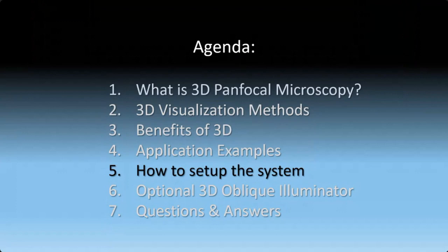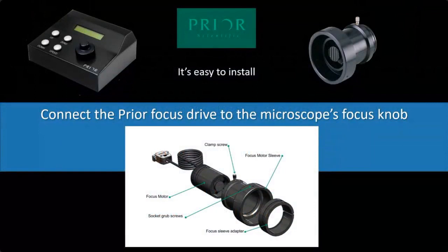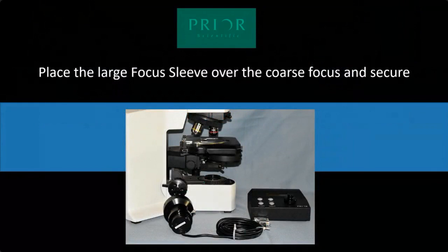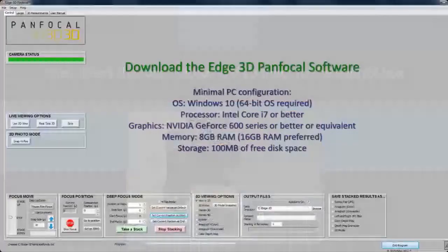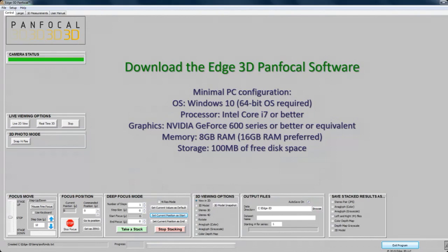Let's talk about how to set up the system — it's very easy. You start by connecting the Prior focus device to your microscope's focus knob. Here's a picture of it on an old Olympus microscope — you put it over the knob and tighten it down, then connect it to the software. You'll need a PC with Windows 7 or later, ideally Windows 10, and a good graphics card. The software interface controls the focus movement.